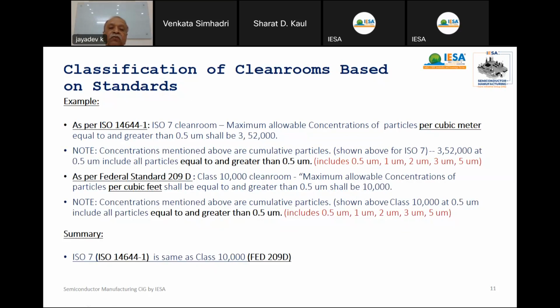Okay, but in validation, the concentrations mentioned above are cumulative particles. That is, 3,52,000 particles at 0.5 micron includes everything equivalent to or greater than 0.5. Apart from that 0.5, it includes 1 micron, 2 micron, 3 up to 5 microns for the microparticle range. Up to 5 micron, whatever reading you get from 0.5 micron is recorded for validation purposes. Same thing if you see Federal Standard, it is equal to 10,000 particles of 0.5 micron per cubic foot. So this concentration I already explained. So ISO 7, which is equal to class 10,000.